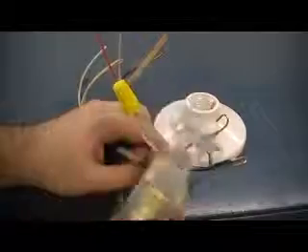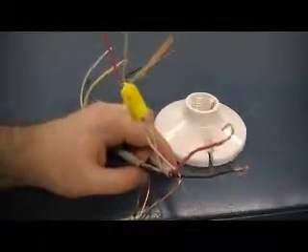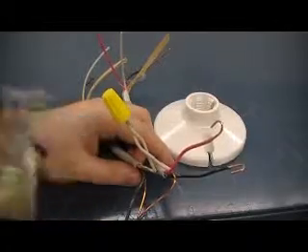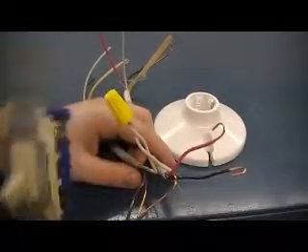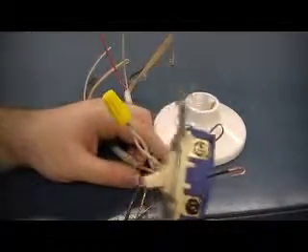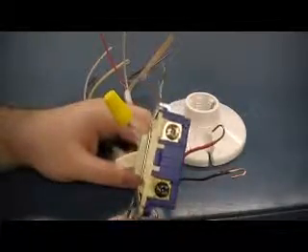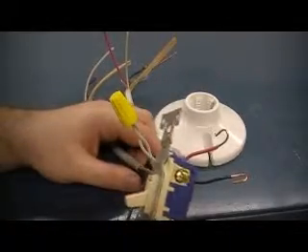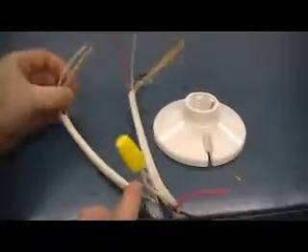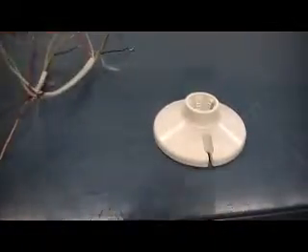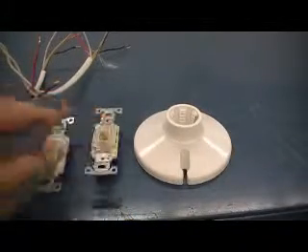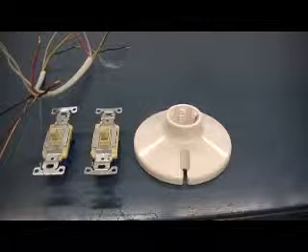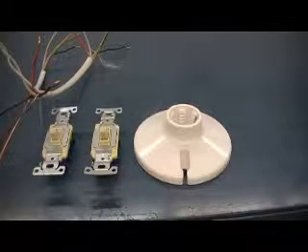Okay, so the rule I always like to use with three-way switches is in on the common, out on the common. So power coming in will go in on the first common on the three-way switch, and power going out on the second common of the second three-way switch. Okay, so if you remember that rule, that'll help you out. In on the common, out on the common. Okay, and then your 14-2 there will go on to connect to your light. Okay, we've discussed how it wires up in a previous video, so if you need to look at that, check out the other video. Okay, but that is the three-way switch circuit.